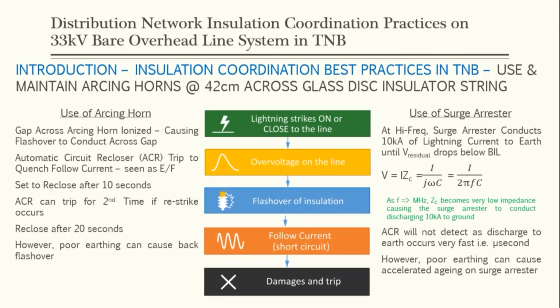Okay, so with the use of surge arrestor at high frequency, the surge arrestor conducts 10 kA of lightning current to earth until the residual voltage drops below the BIL. At a very high frequency, the impedance of the surge arrestor will become very low, causing it to conduct, discharging 10 kA to ground. If you can see the formula, when the frequency becomes very, very high, the impedance will become very low, close to zero. So it will be seen as a short circuit, and that's why the 10 kA can be conducted down to ground.